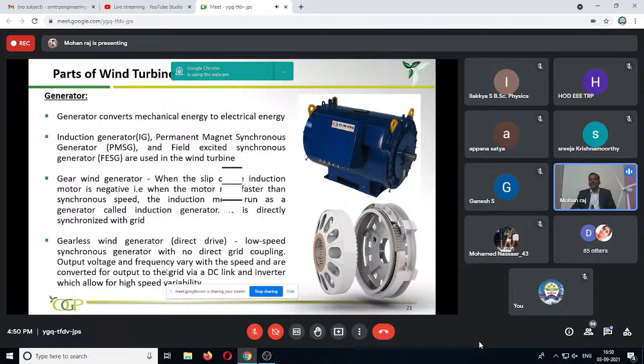For a direct drive generator, it will not. It will generate a variable voltage. So it will generate variable alternating current voltage, and the frequency is also variable. So we need to convert this variable voltage to direct current, and then further it is converted to fixed alternating current and fixed frequency to pump to the grid. So in a direct drive train, a lot of interfaces are required. We can see this in detail in upcoming slides.